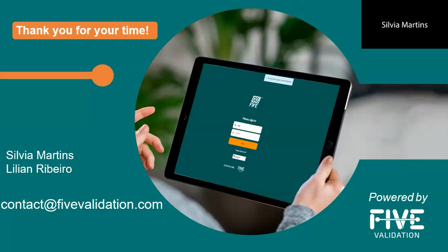And when we have interfaces, we already consider it at least category 4, because interfaces are quite specific to processes, since each company will interface one tool with another tool. In this case, we can produce a functional specification to detail it better. And it's quite interesting for us to sustain the system, because 2 years after the implementation, we can have employee rotation, we can lose someone. If you have it in a documented way, it's pretty important for you to sustain the system, to proceed with periodic reviews and to assess change management as well. So it's crucial.